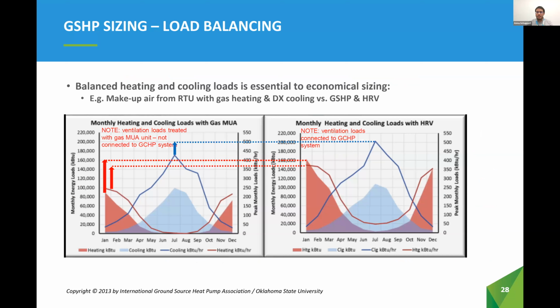Load balancing is extremely important for the long-term reliability and performance of ground source heat pumps, perhaps even more so than for air source heat pumps, because the ground can be considered a thermal battery. Ideally, the same amount of heat is exchanged for heating and cooling on an annual basis. But if these loads are not properly balanced and the ground heat exchanger is not properly sized, it can become frozen or overheated, limiting the performance of the unit or limiting functionality entirely.